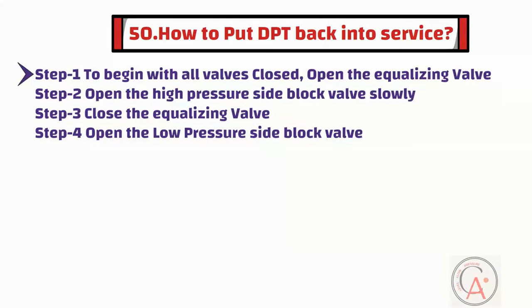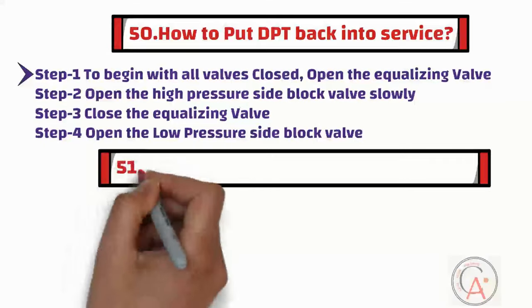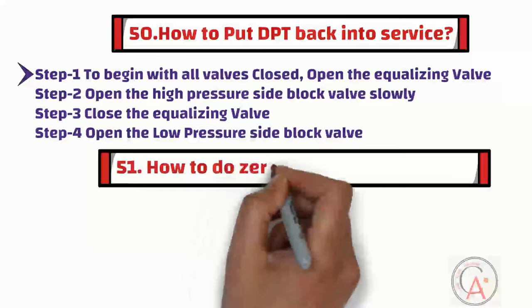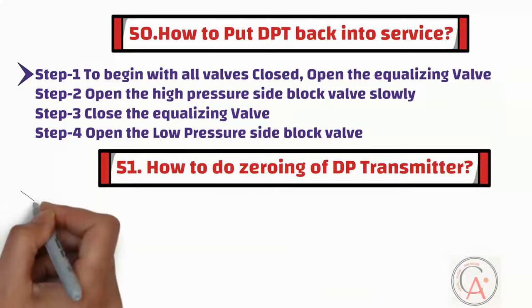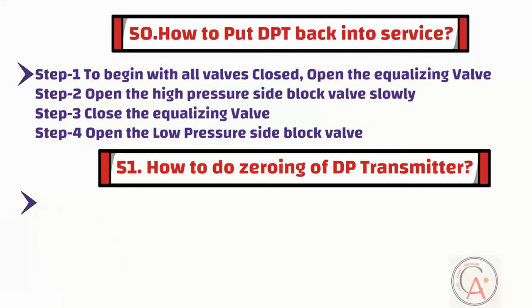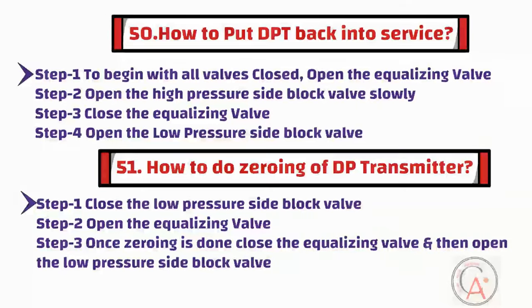Question fifty-one is: how to do zeroing of a DP transmitter? To do zeroing of the transmitter, first close the low-pressure side block valve. Then in step two, open the equalizing valve. Finally, once zeroing is done, close the equalizing valve and open the low-pressure side block valve.